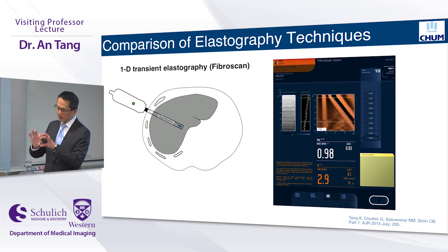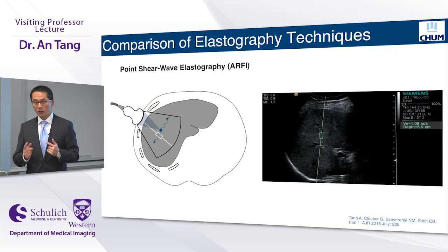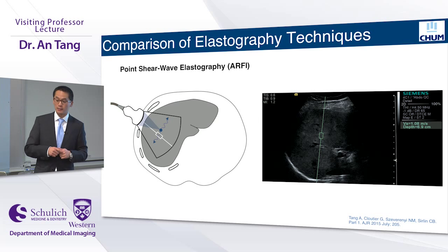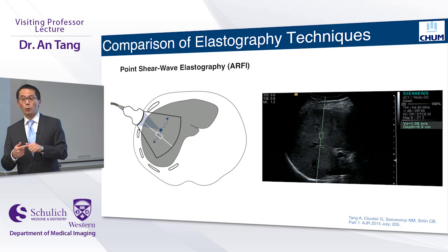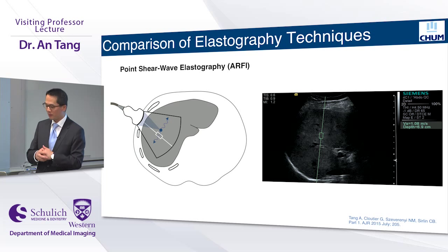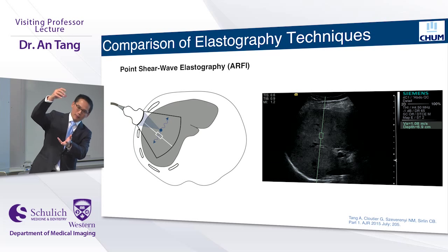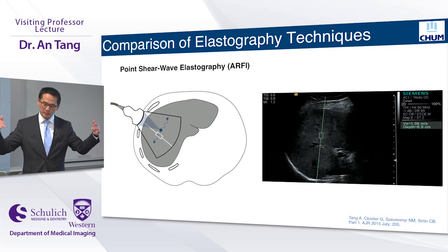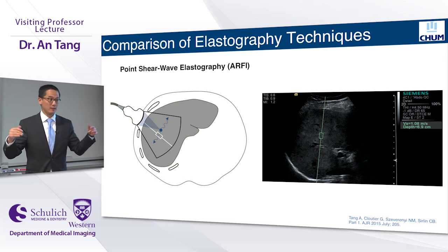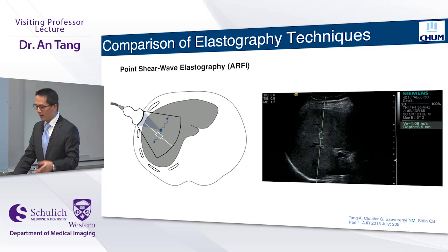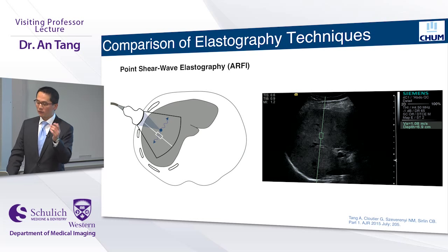Typically, users perform 10 measurements, and the system reports the median and interquartile range to assess measurement validity. More recently, elastography techniques have been implemented into clinical ultrasound systems, known as point shear wave elastography, also commercialized as acoustic radiation force impulse (ARFI). The idea is that we focalize an ultrasound beam in an area, and like a pebble dropped in a pond, it generates waves traveling sideways. We measure the speed of these waves, which travel slowly in soft tissue and more rapidly in stiff or cirrhotic tissue. An advantage is that we can use B-mode imaging to place a region of interest away from vessels and the capsule.